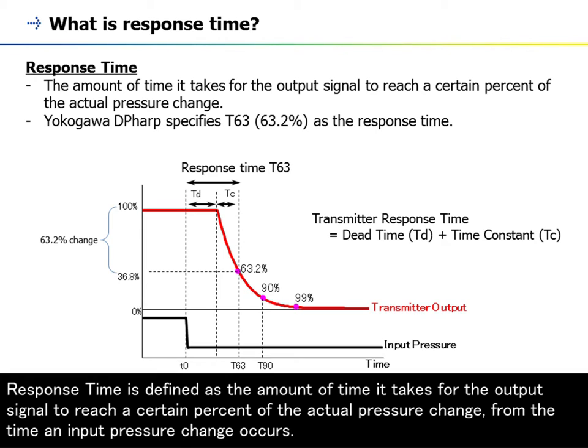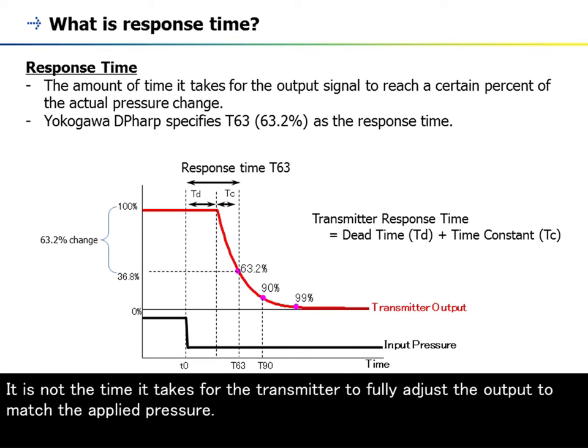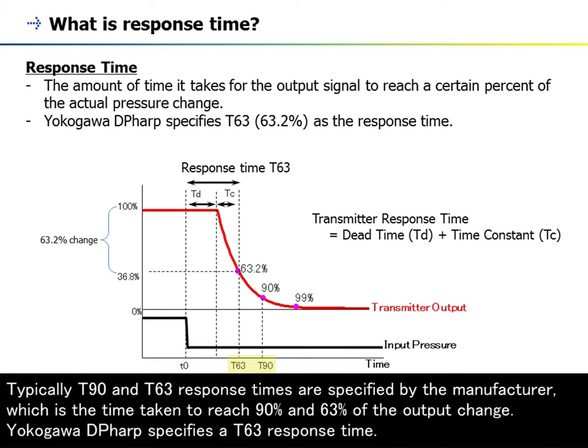Response time is defined as the amount of time it takes for the output signal to reach a certain percent of the actual pressure change, from the time an input pressure change occurs. It is not the time it takes for the transmitter to fully adjust the output to match the applied pressure. Typically T90 and T63 response times are specified by the manufacturer, which is the time taken to reach 90% and 63% of the output change.